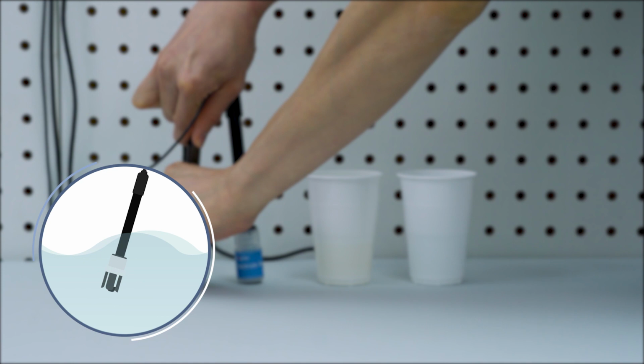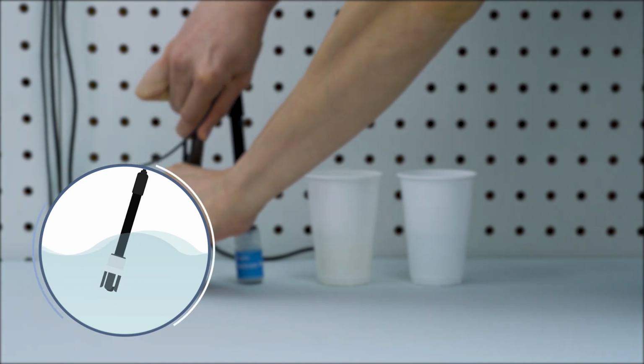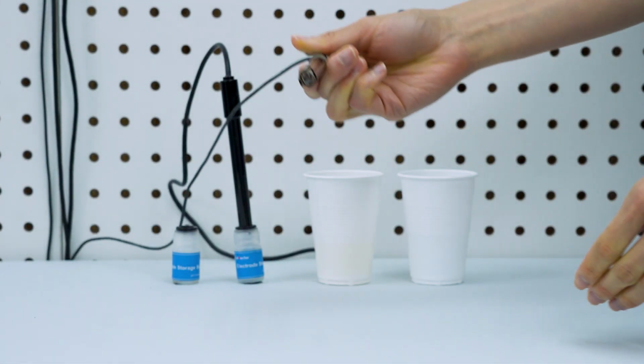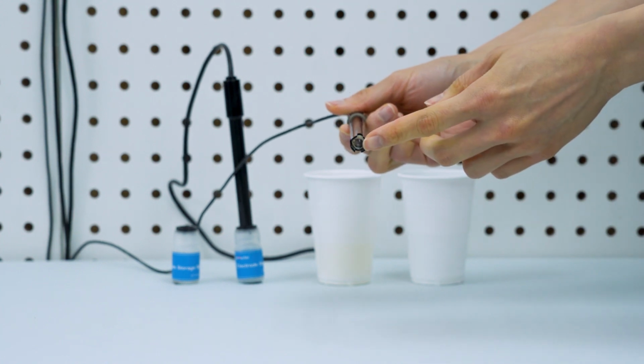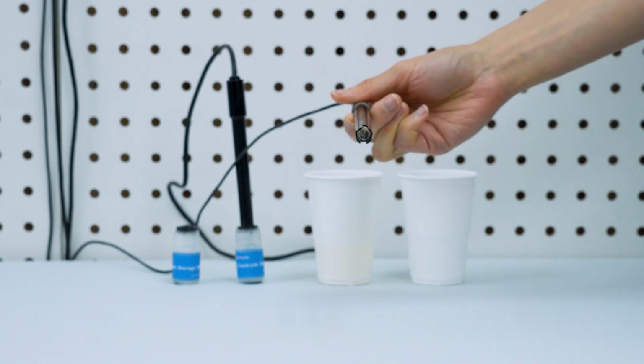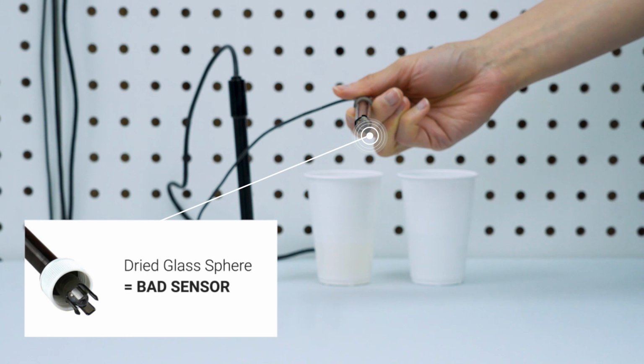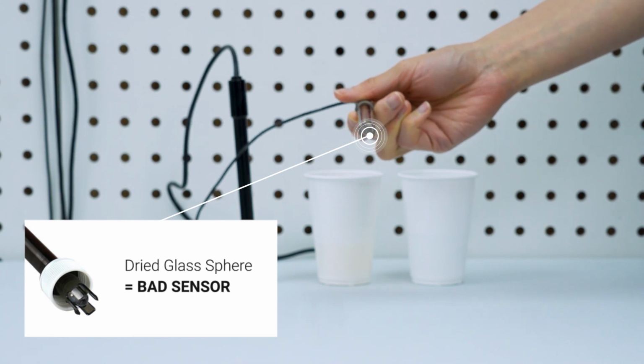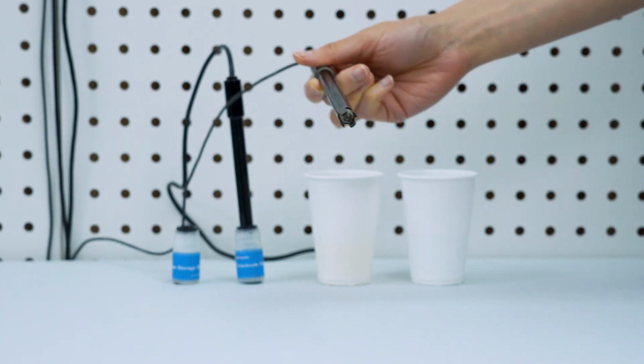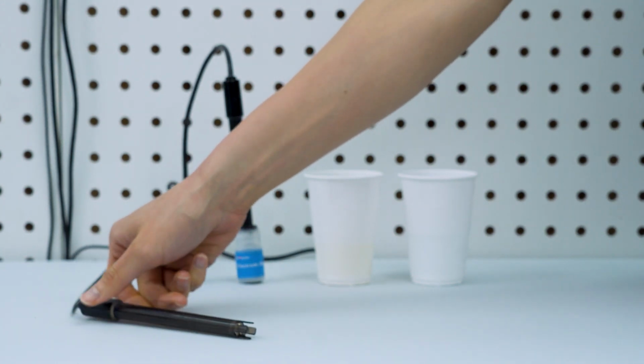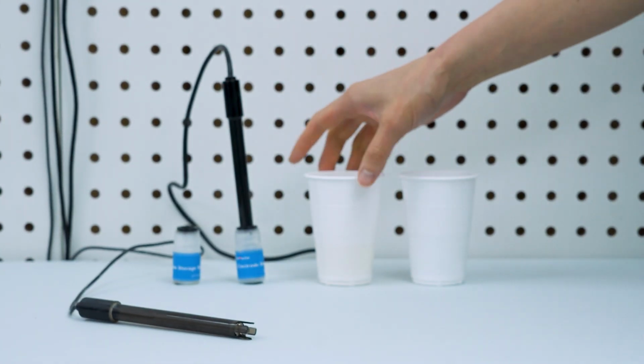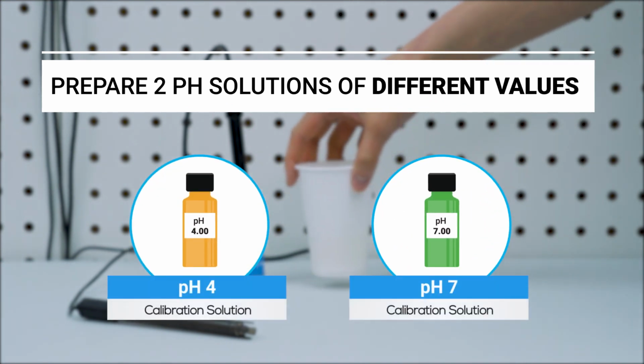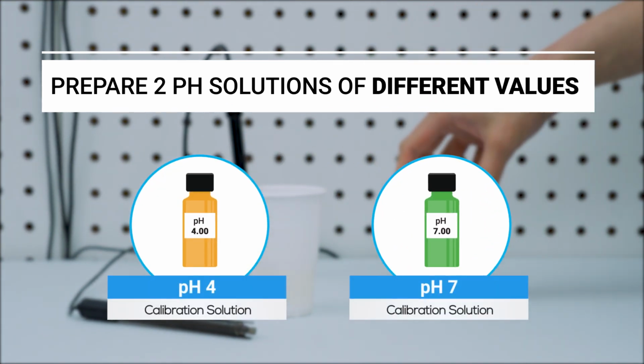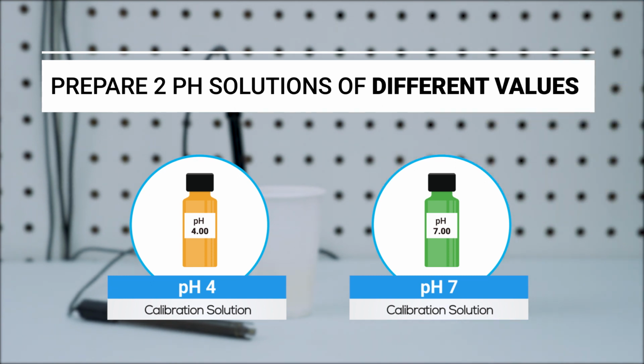The pH sensor has to be soaked with liquid all the time, or else it could go bad easily. You can see here there's a sphere of glass at the tip of the sensor, filled with liquid. If it's all dried up, very much possible it's a bad or defective sensor. To calibrate it properly, prepare 2 different values of the pH solutions. Usually, it's a 4 and 7.